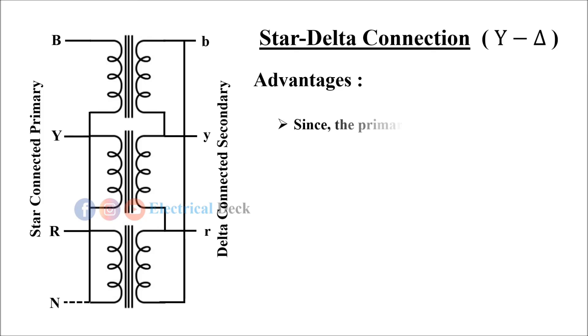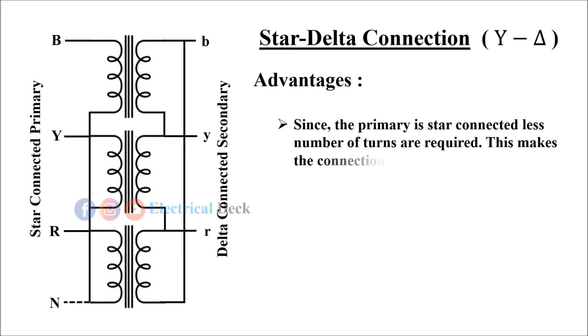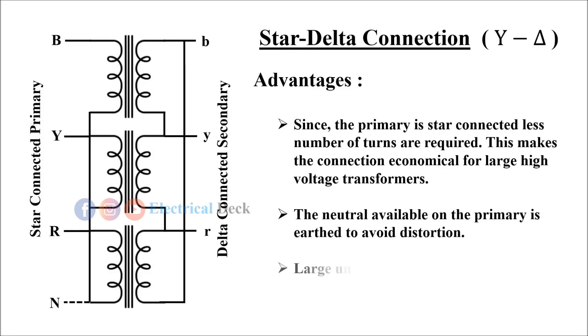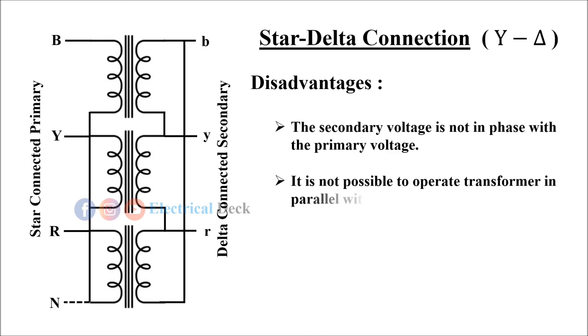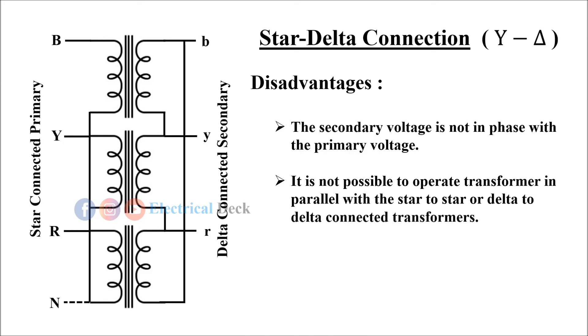The advantages of star-to-delta connection are: since the primary is star-connected, less number of turns are required, making the connection economical for large high-voltage transformers. The neutral available on the primary is earthed to avoid distortion, and large unbalanced loads can be handled satisfactorily. But the disadvantage is that the secondary voltage is not in phase with the primary voltage, and it is not possible to operate this transformer in parallel with star-to-star or delta-to-delta connected transformers.